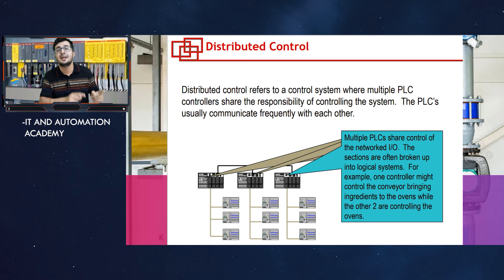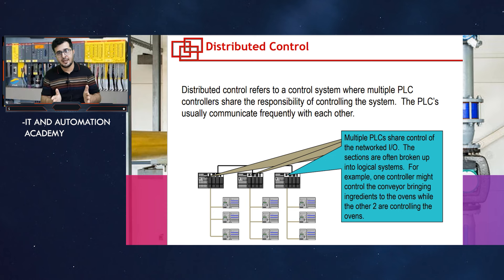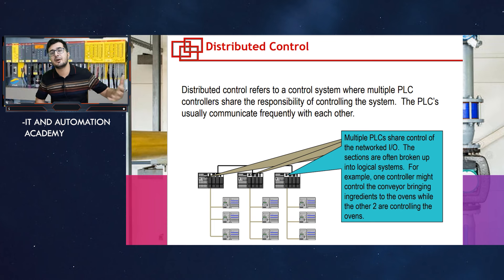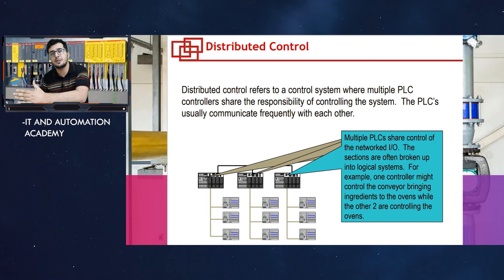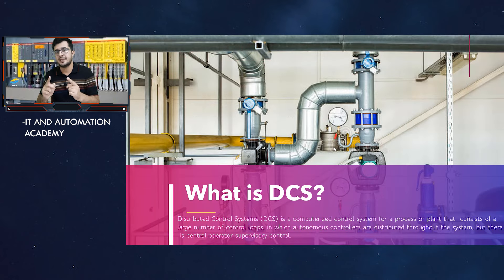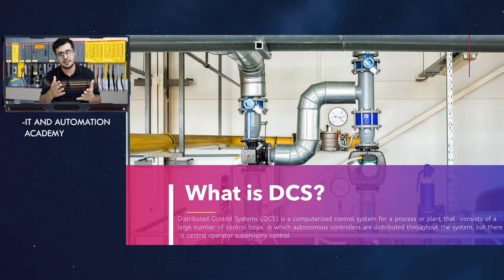The basic concept of distributed control is that you take different areas and each controller takes care of a specific area. The advantage is that if your unit B controller fails, units A and C have no effect — they would still be running. This is the beauty of distributed control, which we have seen in both PLC and DCS.